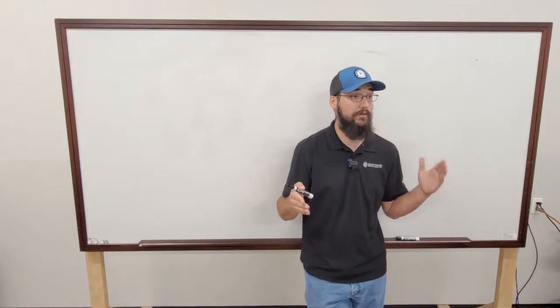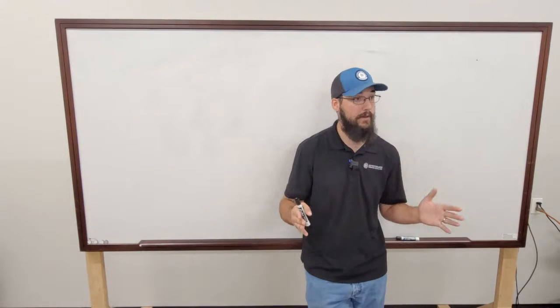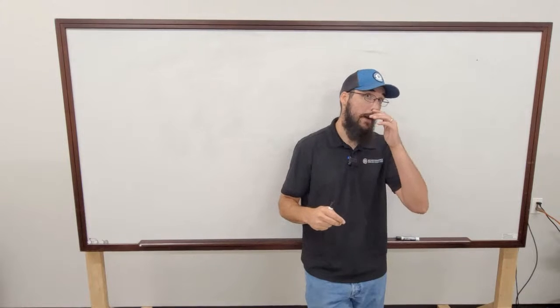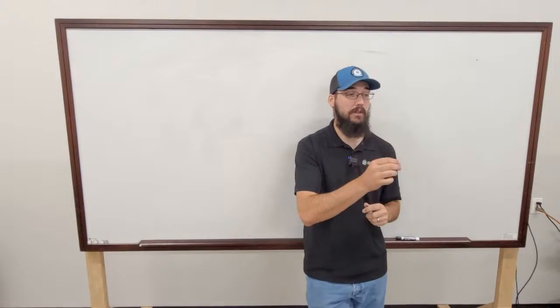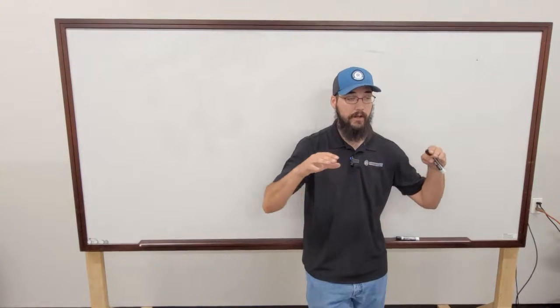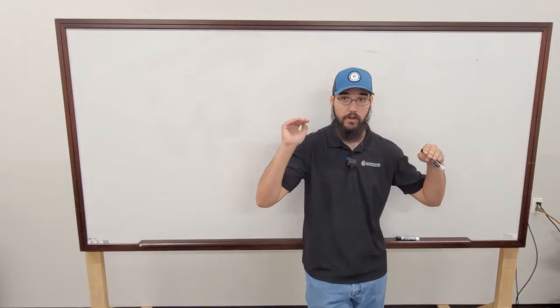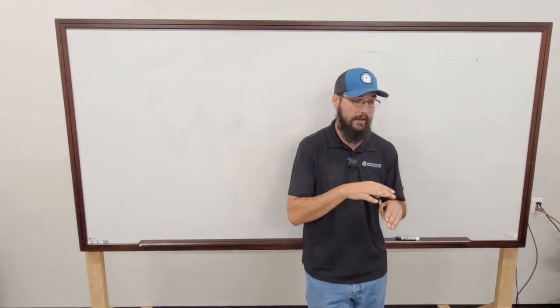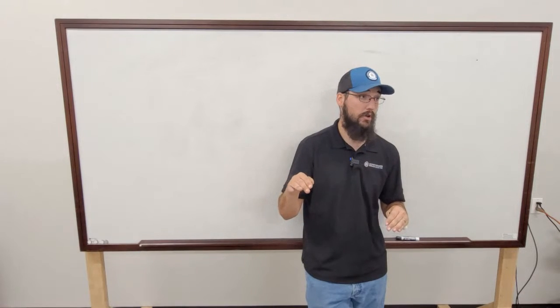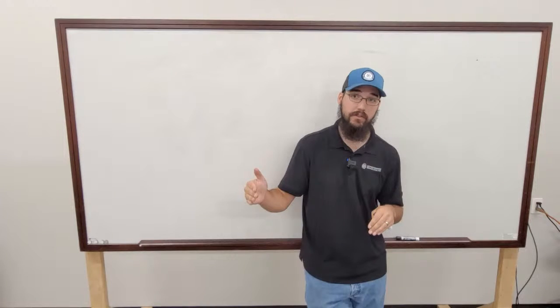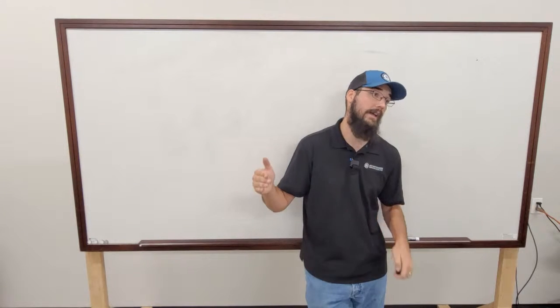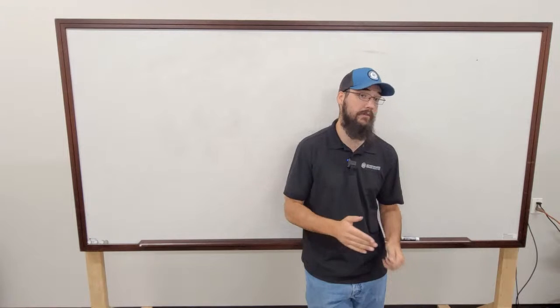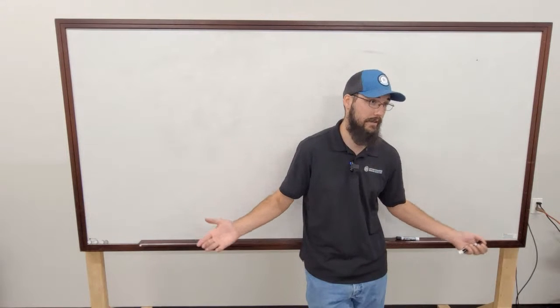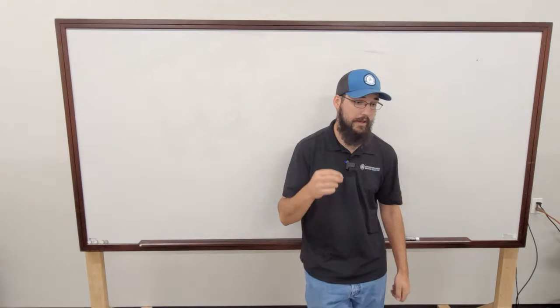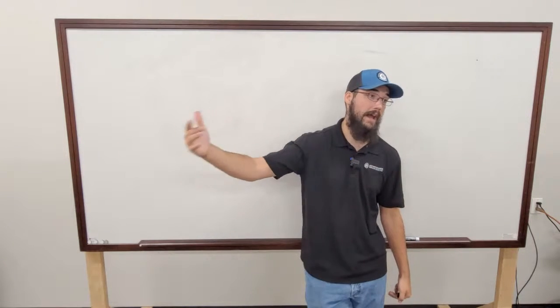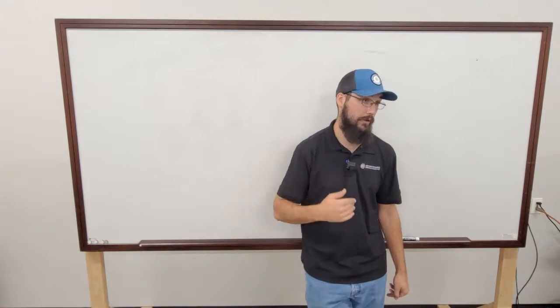So just in terms of starting up and shutting down, just bear that in mind. As I was talking about earlier, for it to stage up the other circuit, it's looking at the RLA. So if that circuit stages up to 100% RLA and we're still not satisfying set point for, say, 5 minutes, then it's going to say, okay, I need to bring in another circuit to help me out.